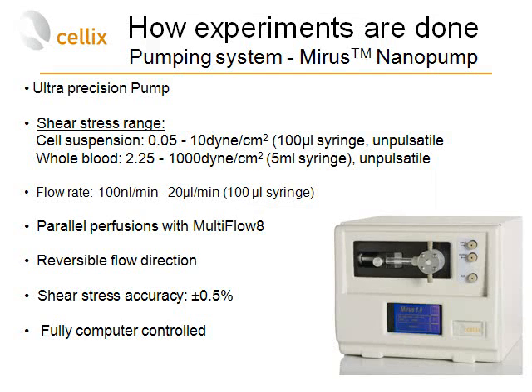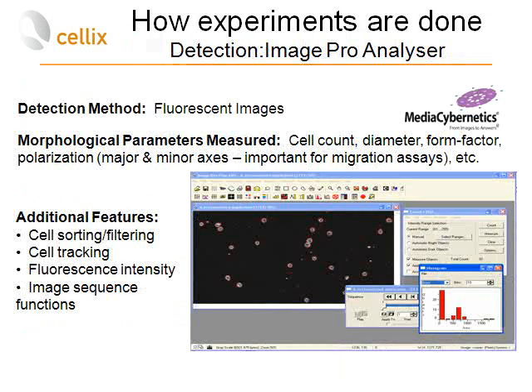To manipulate liquids and pump cells and whole blood within the micro-channels, we recommend the Mirus nanopump. It is an ultra-precision pump covering a range of shear stresses from very low vascular shear stress to high arterial shear stress. It can perfuse up to eight channels in parallel, has reversible flow direction, and is fully computer-controlled during the assay.